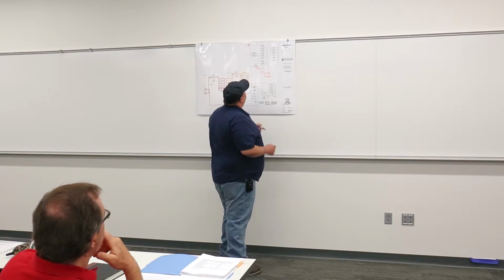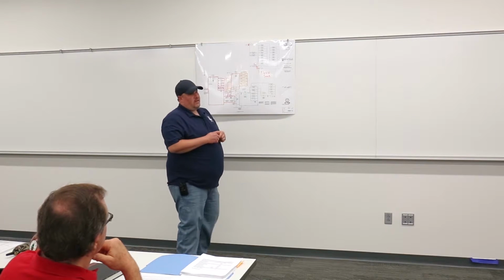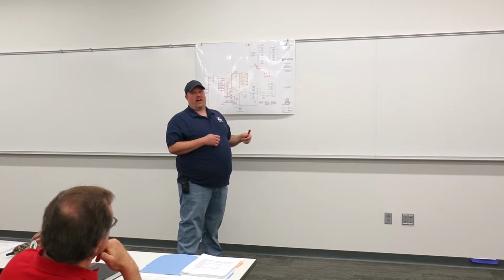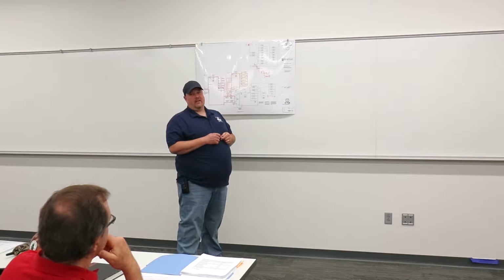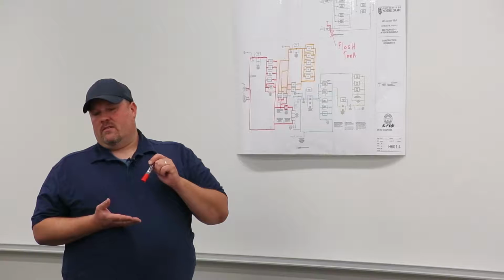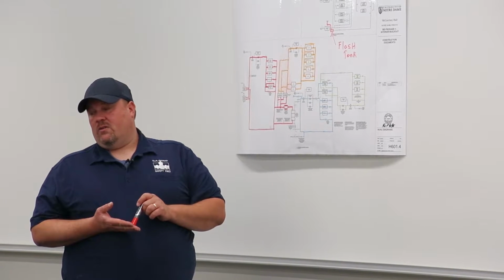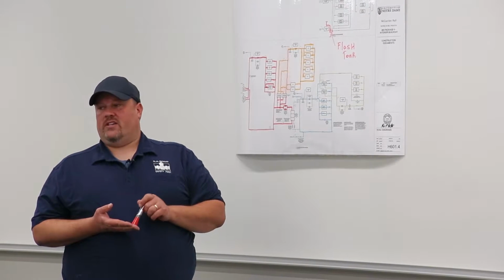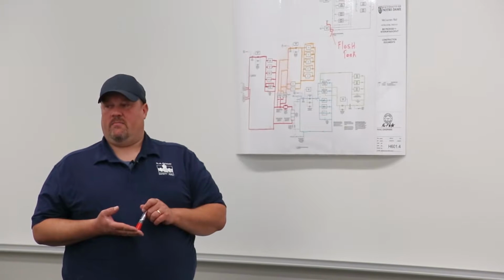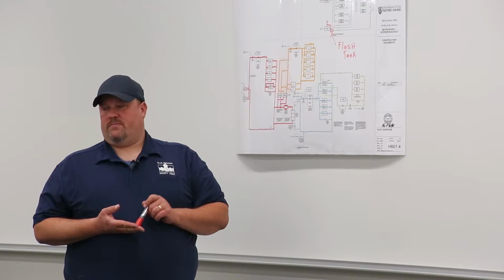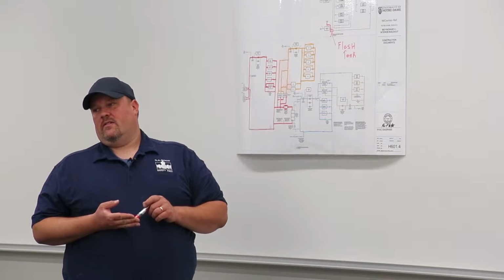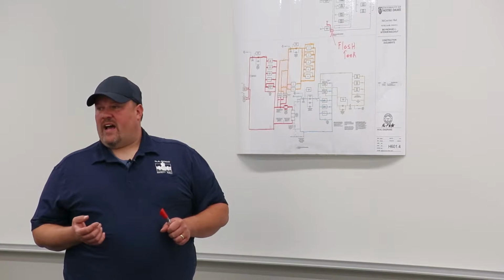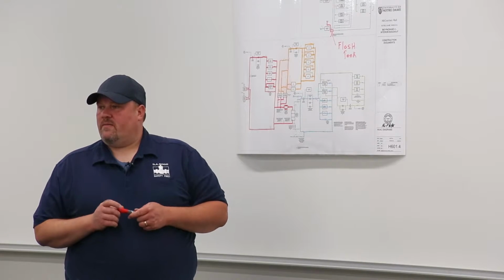They can be shut off inside the building, and back at the branch section coming off the tunnel, there's another set of valves. There's actually a double set of valves to be able to shut the system down. And that's for low pressure, medium pressure, condensate lines. Actually, I do believe all systems. As it branches off from that tunnel and as it comes inside the building, there's valves on each section. So in the gist, we've got valves that are 30 feet apart.